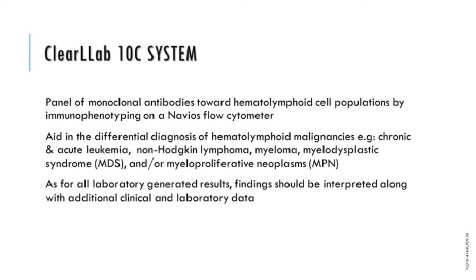The ClearLLab 10C system was designed for the Beckman Coulter Navios and Navios EX flow cytometers as an aid in the differential diagnosis of hematolymphoid malignancies — for example, chronic and acute leukemia, non-Hodgkin's lymphoma, myeloma, myelodysplastic syndromes, and myeloproliferative neoplasms. A key point is that the reagents are pre-titrated in a dried format and stable at room temperature for over 12 months, so a single batch could be ordered for the entire year. While it does consist of a complete system for flow cytometry including controls and analysis, results form only a part of the overall decision-making process in arriving at a patient diagnosis.